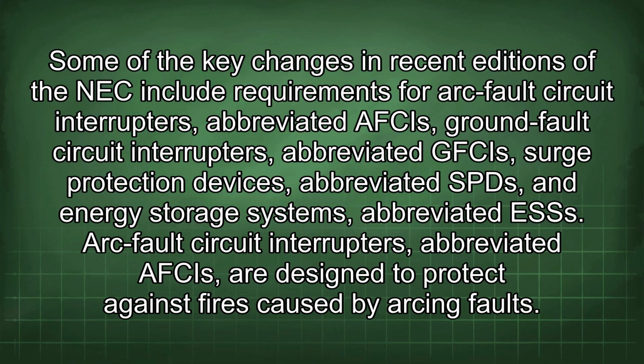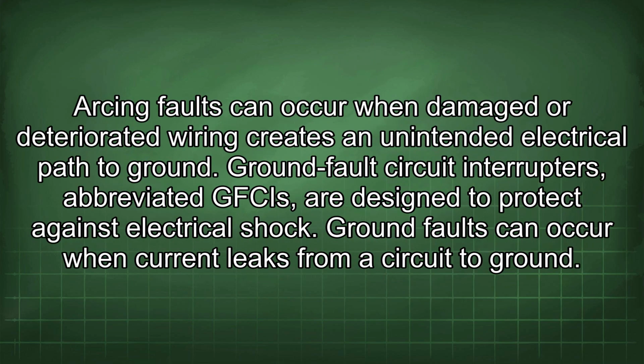Arc fault circuit interrupters, abbreviated AFCIs, are designed to protect against fires caused by arcing faults. Arcing faults can occur when damaged or deteriorated wiring creates an unintended electrical path to ground. Ground fault circuit interrupters, abbreviated GFCIs, are designed to protect against electrical shock. Ground faults can occur when current leaks from a circuit to ground.